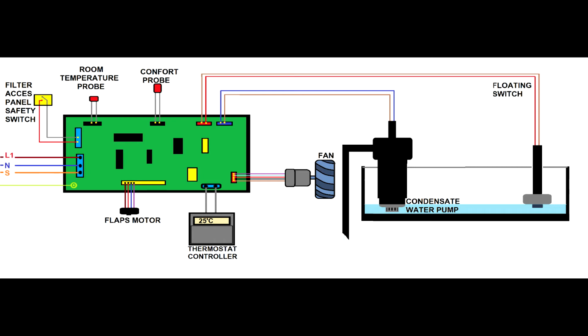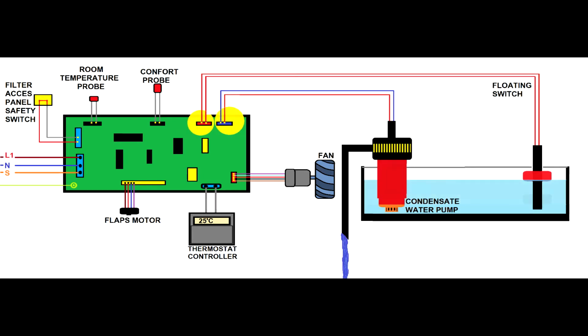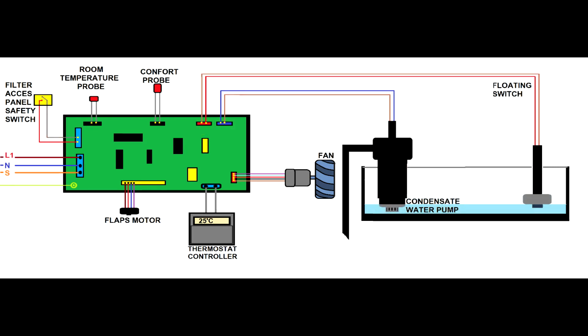Okay, so the floating switch will enable a switch when it goes up, because it's a magnetic switch, and it will enable the pump, and the pump will drain the drip tray. But what if we have sludge, if we have dirt, if the pump is contaminated? What if the floating switch shaft is contaminated? Sometimes we have to clean them. That's not a pleasant job, but if you don't clean them, you won't have any success. You really have to pay attention to this.